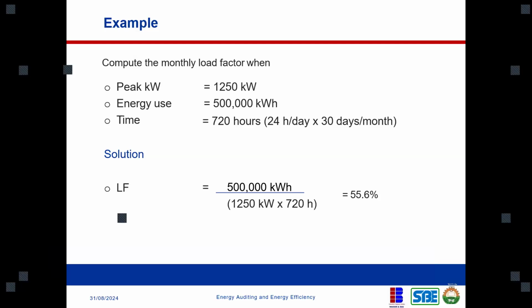So when you want to compute the load factor, it becomes the actual energy consumption, which is 500,000 kilowatt hours, divided by the peak demand, which is 1,250 kilowatts, times the hours, which is 720. Once you do that, you get 55.6%. 55.6% is not bad, but in our design processes, let us please aim at 70%. In our design system, when you're sizing generators for facilities, try to see how you can maintain a load factor of 70%.